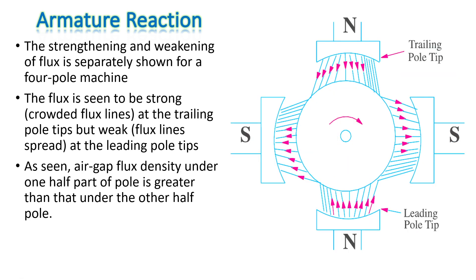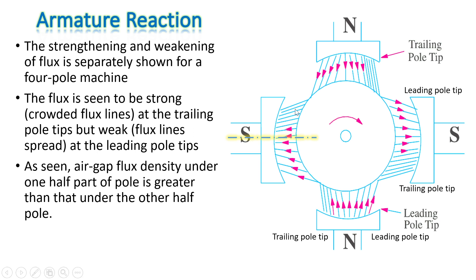The strengthening and weakening of flux is separately shown for a four-pole machine. Flux is strong at the trailing pole tips but weak at the leading pole tips, indicated by crowded and spread-out flux lines respectively. The air gap flux density under one half of the pole is greater than the other half — so one half has a strong magnetic field and the other half has a weak magnetic field.